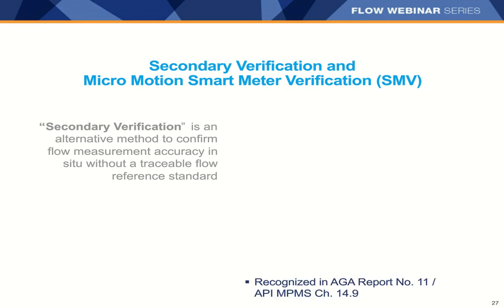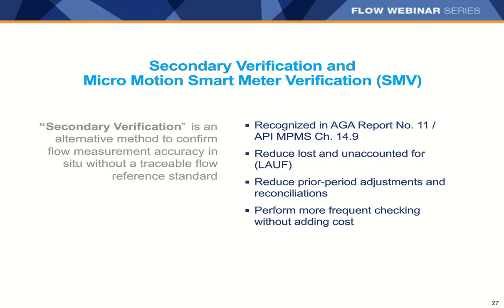AGA11 acknowledges that valid secondary verification methods may be used to bolster measurement confidence of Coriolis meters in natural gas applications. Smart meter verification is a low-cost in-situ method — no flow interruption, no need to take the meter out of service and send it back for recalibration. Most likely you'll get back an 'as-left, as-found' result, indicating the issue was inside the process rather than the meter. The inspection report can be printed from ProLink 3 or AMS for quality records.